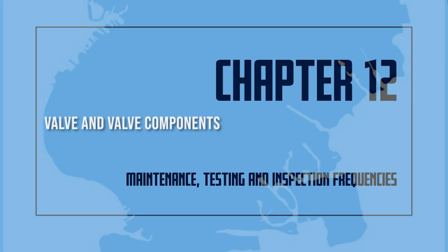D. Valve and valve components. Pre-action/deluge valves. The valve enclosure heating equipment is subject to freezing and shall be inspected daily during cold weather for its ability to maintain a minimum temperature of at least 40 degrees Fahrenheit. Valve enclosures equipped with low temperature alarms shall be inspected weekly during cold weather. Exterior valves shall be externally inspected monthly to ensure that they are free from physical damage, the valve seat is not leaking, all trim valves are in the appropriate open or closed position, and electrical components are in service.